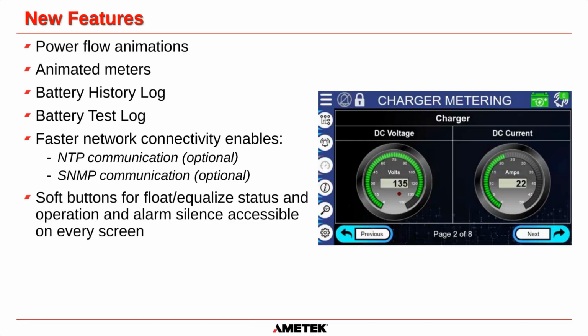Since we got rid of the keypad, we lost the hardware buttons for float, equalize, alarm silence and lamp test. The float and equalize status can be changed by clicking on the battery icon in the top right, like we discussed on the last slide. I forgot to mention that when a system is in equalize and the battery is amber, if you click on it again, it'll change it back to float. Since we don't have an alarm silence button, the alarm silence icon on the top left of the menu, which is always displayed, is available.